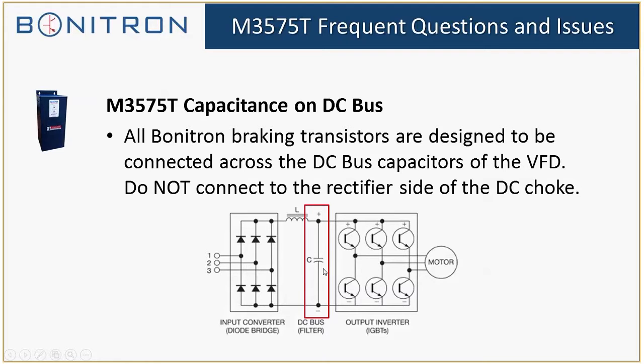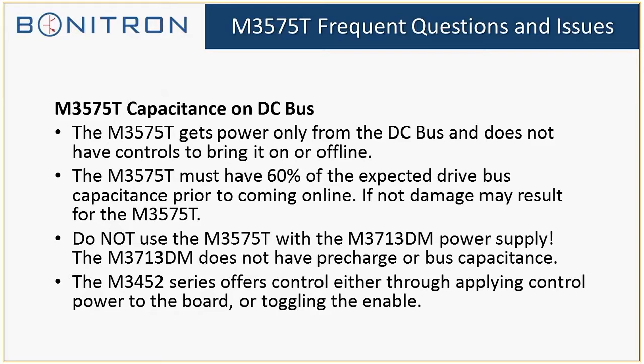A lot of drive manufacturers also have braking terminals for their resistors. While it's not necessarily bad, our unit won't function properly there, and the drive will fault out on overvoltage. So the importance of the 3575T is that it really needs to have capacitance on the DC bus. If you haven't had the chance, I really recommend you read section 7.3 of the 3575T manual. It has a great page about how and why all our braking transistors, including the M3452 and this very small M3575T, need to have capacitance on the DC bus.